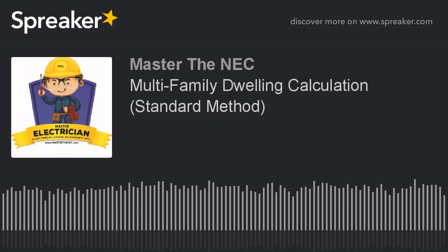So I do the same kind of thing. I determine what I need to handle the load, and then I determine how many sets I'm going to need in order to do that. So I can parallel. But at the end of the day, I have to take all those things into consideration. All right, but that kind of shows you how you can take the neutral conductor and apply the demands to it, which you thought would have been 489 amps.